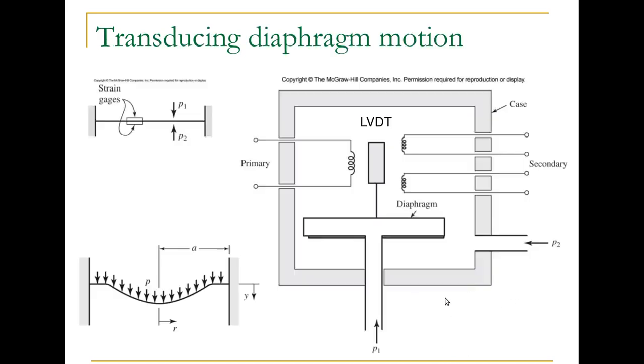And a couple of means for measuring the deflection are to use strain gauges on the diaphragm. So that incorporates materials, mechanics of materials theory, in order to get the displacement from the strain. Or we could measure the displacement directly here with an LVDT. You could also use a capacitive displacement transducer. Any way of measuring the displacement directly can give you pressure.